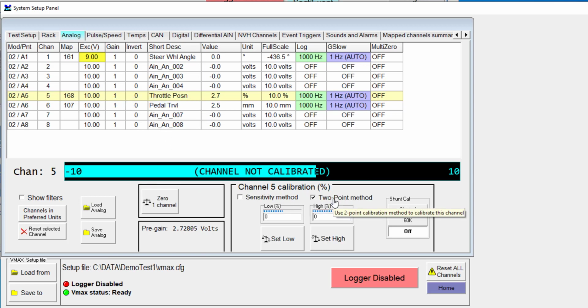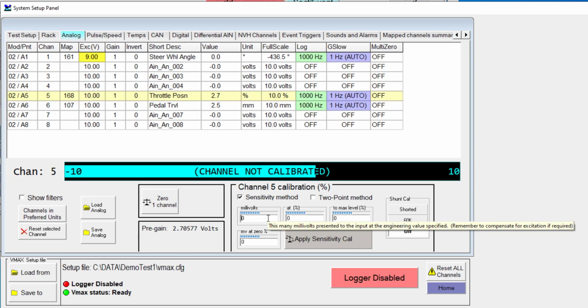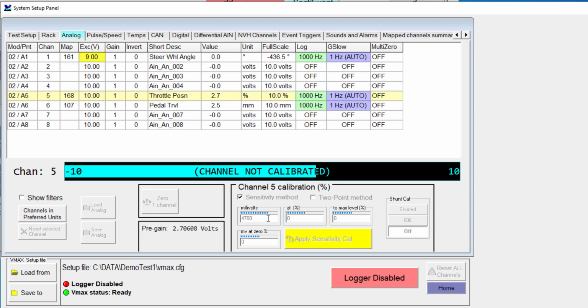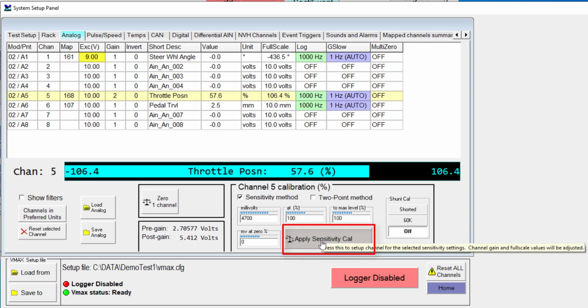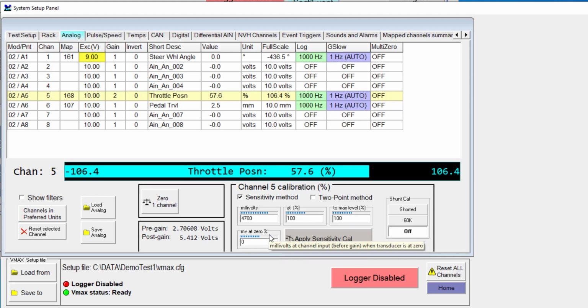And this time, instead of doing a 2-point calibration, I'm going to use the sensitivity. So essentially, it's about 4.7 volts to get 100% throttle. So if I switch this to the sensitivity method, and I say that 4.7 volts is 4,700 millivolts at 100% throttle to a maximum level, this is how it's going to set up my gain for me. Okay, so I can apply the sensitivity right now, but because I didn't enter a millivolts at 0%, my zero offset is going to be off. So we can tell right now that as I am not putting my foot on the throttle, we have a voltage of about 2,700 millivolts.